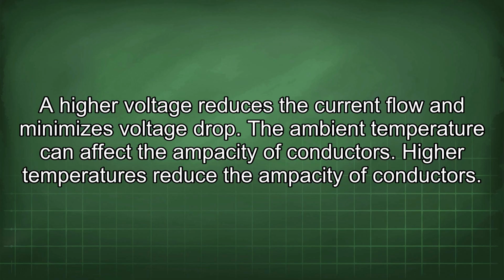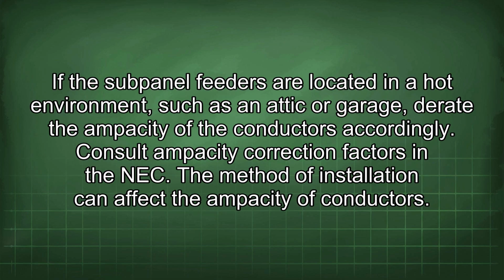The ambient temperature can affect the ampacity of conductors. High temperatures reduce the ampacity of conductors. If the subpanel feeders are located in a hot environment, such as an attic or garage, derate the ampacity of the conductors accordingly. Consult ampacity correction factors in the NEC.